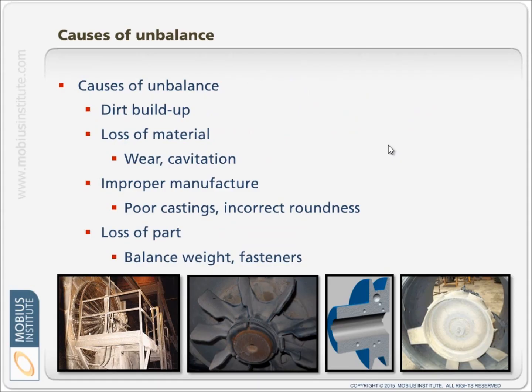Why do we get unbalance? Very commonly in fans, it's just a build-up of dirt. It might be a loss of material through wear, cavitation, erosion, or corrosion. It might be due to poor castings or incorrect roundness — for example, eccentricity. It might be a loss of a part: a balance weight might fall off, a fastener might come away, or there may be loss of part of the coupling. We need to correct any mechanical problems that might exist, like missing blades, and then go through the balance process.